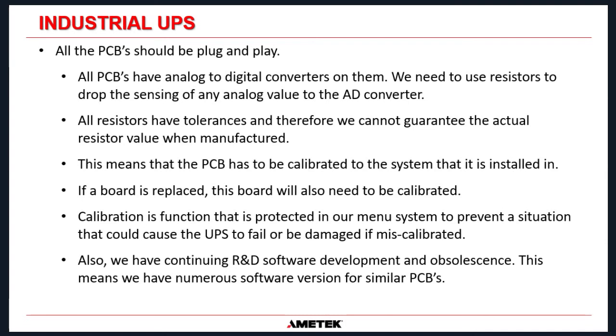And that means we have numerous software revisions for many similar PCBs. So once again, we're in a situation where if we're replacing an old board with a new board, the new board may have a software revision on it, and things need to be changed when we install it. And those changes have to be done by a certified field service engineer who can come and update the system to accept that new board.